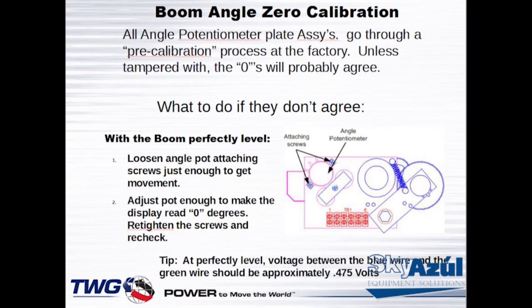I will caution you this, if you're gonna rotate the pot, you need to make sure that alignment is present. I showed you where the little arrow aligns with the crack on the bracket. You need to make sure that's set right, because they like to fiddle with that stuff too. And then you just loosen these screws just enough to move the pot. It's very, very sensitive, really hard to get it on track. But you have that voltage tolerance you can use, and with the software today, you can push a button and 0 it and make it agree. So there's your correction.